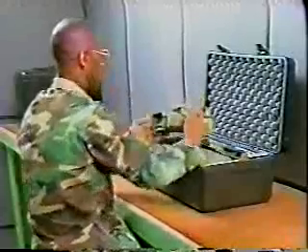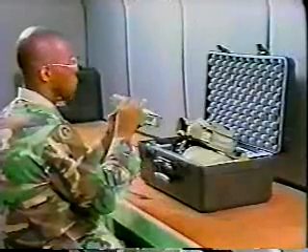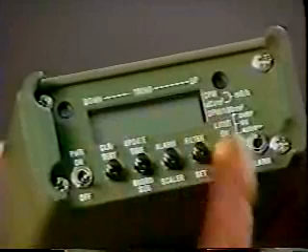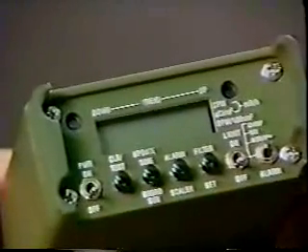The set weighs approximately 27 pounds. The radiac meter is battery powered. It has a cable plug to connect the various probes and an enclosed speaker for audio alarm and chirps. Rates are shown on the display screen. Trend lights indicate an increase or decrease in rates, and also act as visual alarm lights when flashing.